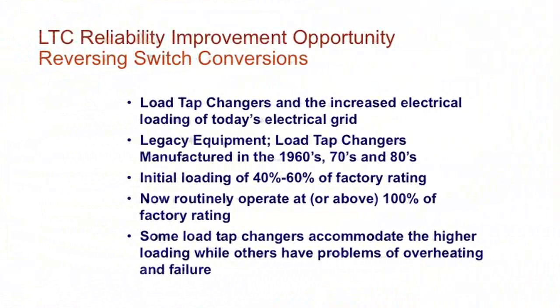A lot of it is tap changers. Basically, the tap changers that we're talking about, they were utilized back in the 60s, 70s, 80s. They were over-designed, basically. They were only operating at 40 to 60% of their capacity. But today, with the extra loading on the units, they're running 100%, or some of them are even running over, and it's creating these problems that we're seeing on these reversing switches. So part of it is we designed something that was not there 40, 50, 60 years ago.